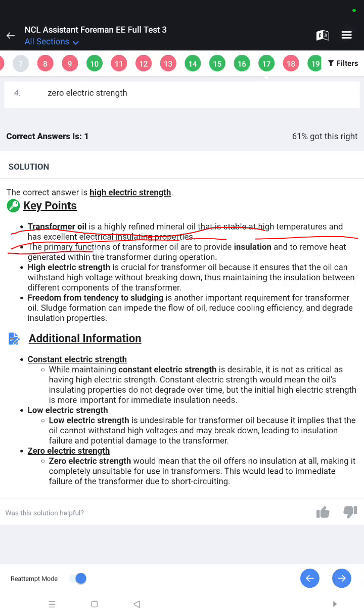Transformer oil is a highly refined mineral oil that is stable at high temperature and has excellent electrical insulating properties. The primary functions of transformer oil are to provide insulation and to remove heat generated within the transformer during operation. High electric strength is crucial for transformer oil because it ensures that the oil can withstand high voltage without breaking down, thus maintaining the insulation between different components of the transformer. Freedom from tendency to sludging is another important requirement for transformer oil. Sludge formation can impede the flow of oil, reduce cooling efficiency, and degrade insulation properties.